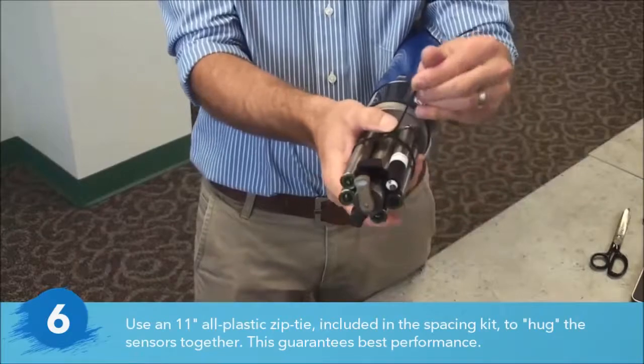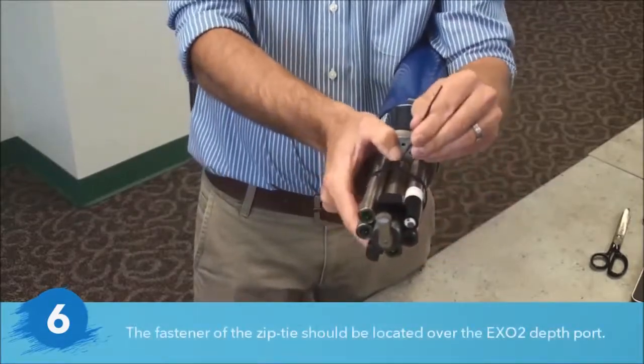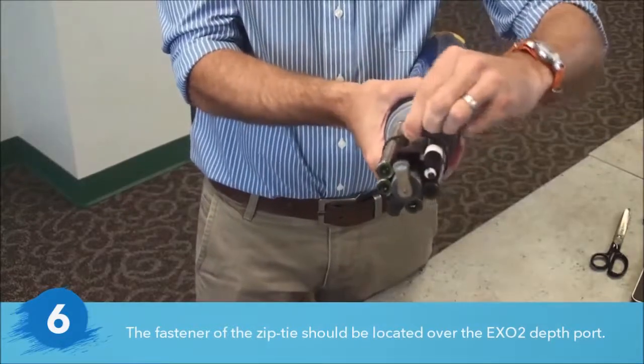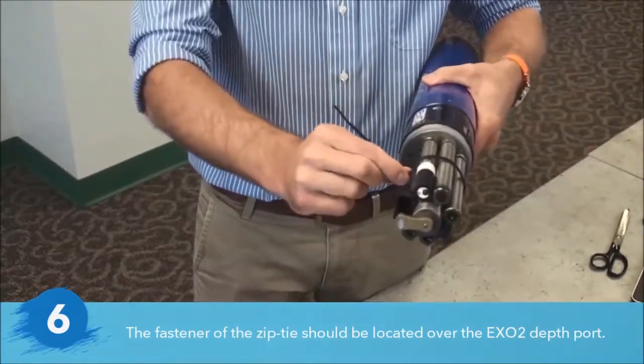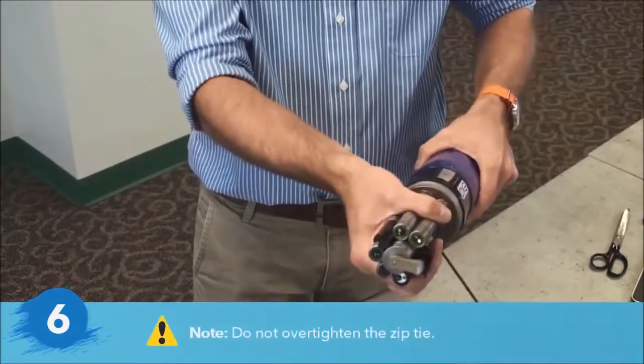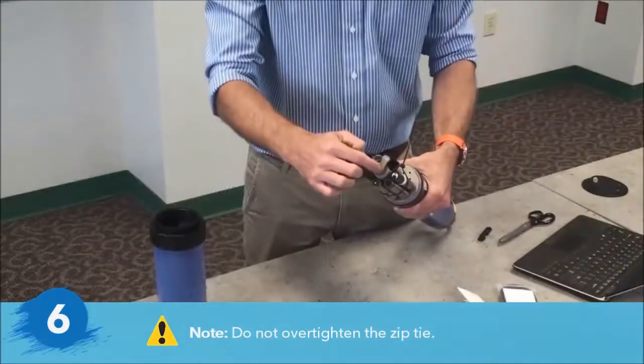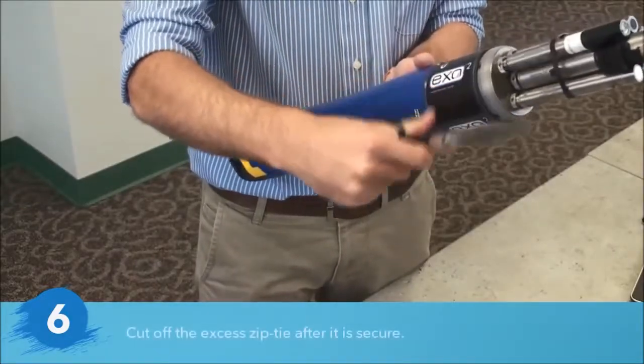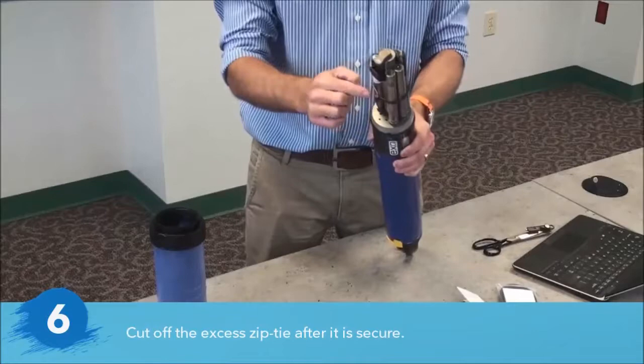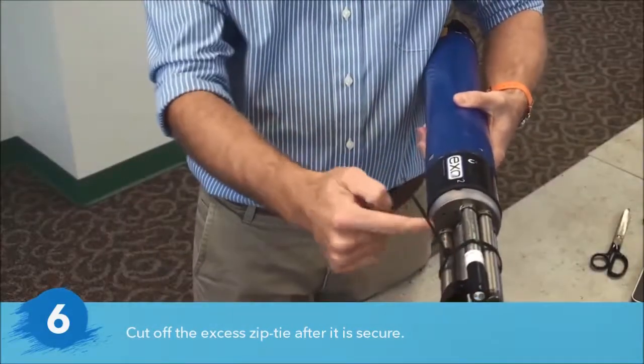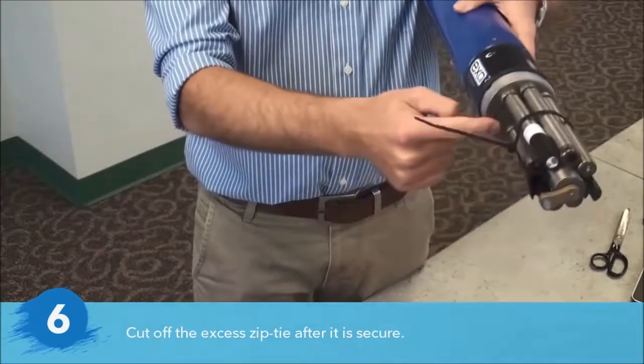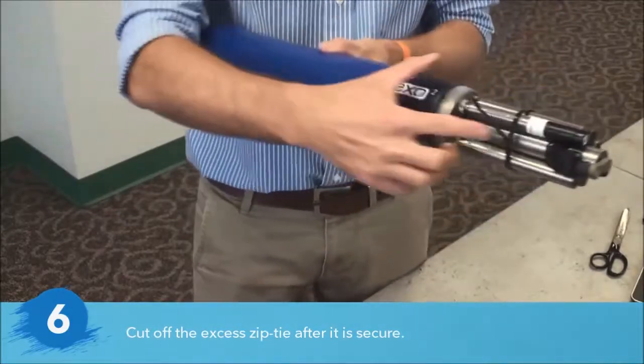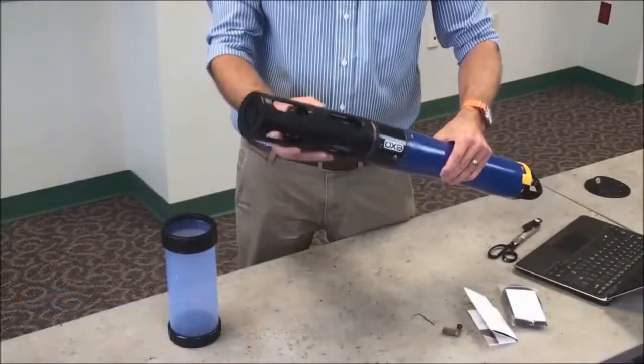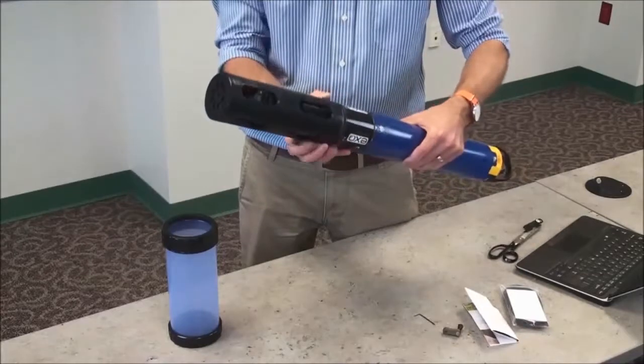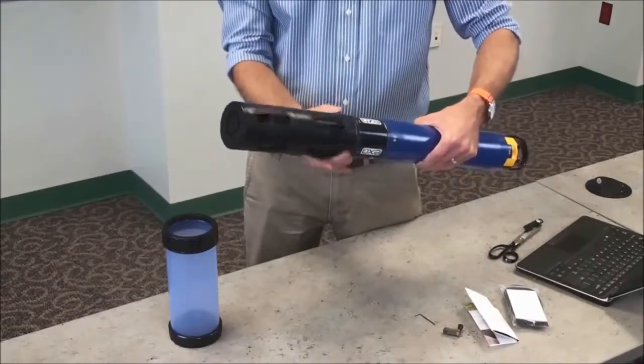We want to keep the nub on the zip tie located at the depth port location. And we just want to snug it up a little bit so that it still moves a little. And we can see that all the sensors are now hugging the central wiper. We can cut off any excess zip tie. We do want to note that the zip tie is located above the depth port. So when I go to install the sensor guard, it's going to go on top of the probes, and there's no interference between the zip tie and the probe guard.